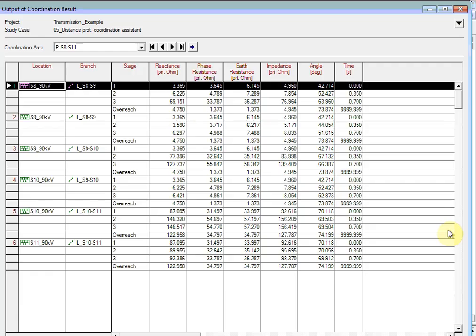You can see that the reach setting of zone 1 is less than the reach setting of zone 2, which is less than the reach setting of zone 3. This is true for all cases. If you want to, you can try to manually calculate these settings based on the rules defined in the manual. If you want to export these results to spreadsheet format or HTML, then press the button in the top right-hand corner as illustrated. Now let's take a look at the coordination diagrams.